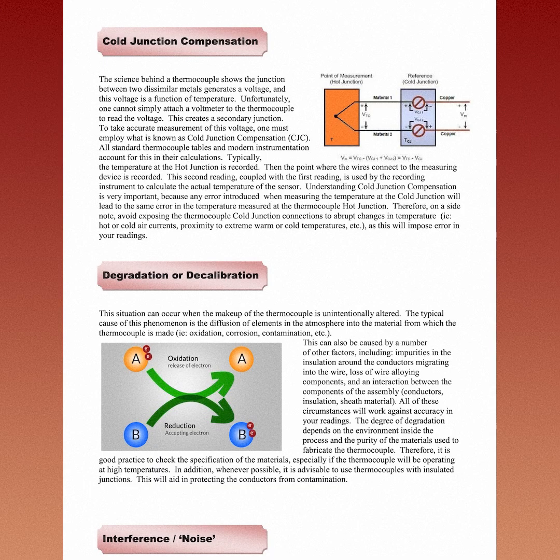Degradation or decalibration. This situation can occur when the makeup of the thermocouple is unintentionally altered. The typical cause of this phenomenon is the diffusion of elements in the atmosphere into the material from which the thermocouple is made, that is, oxidation, corrosion, contamination, etc. This can also be caused by a number of other factors, including impurities in the insulation around the conductors migrating into the wire, loss of wire alloying components, and an interaction between the components of the assembly, conductors, insulation, sheath material. All of these circumstances will work against accuracy in your readings.